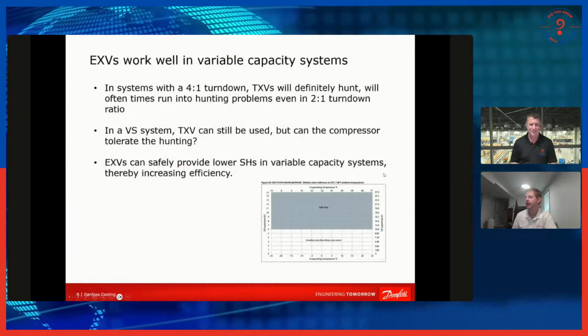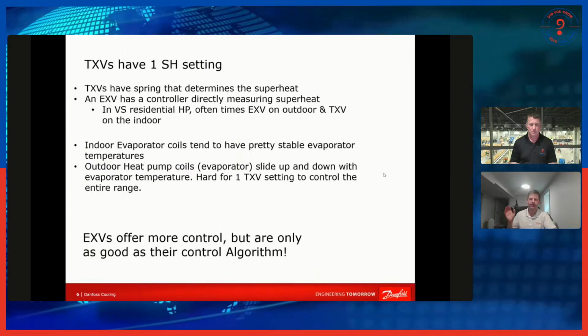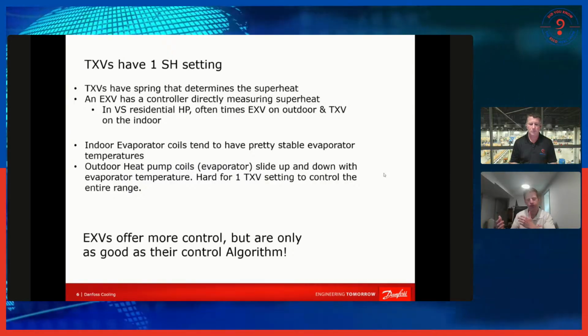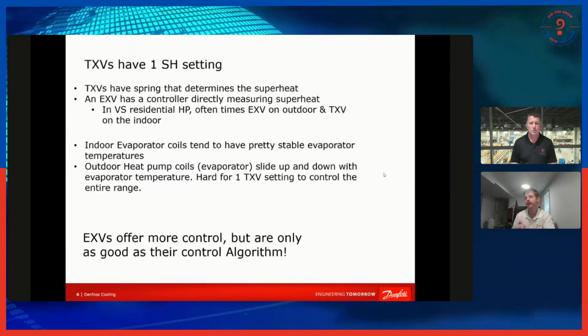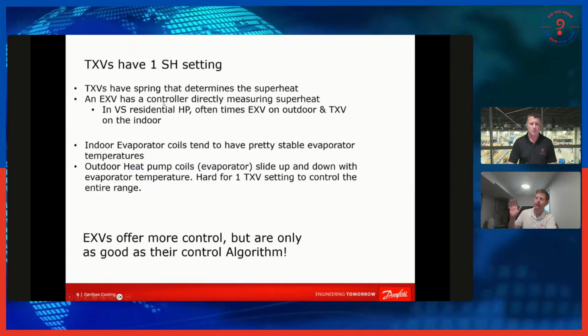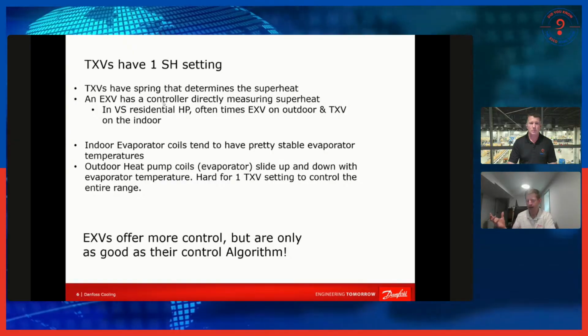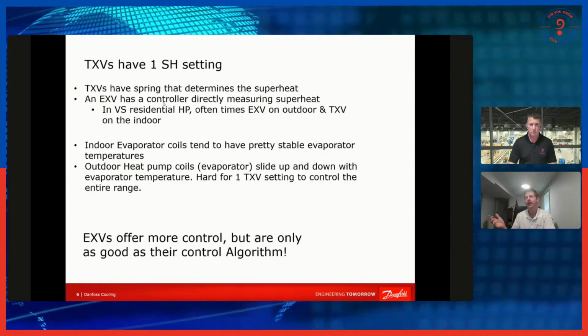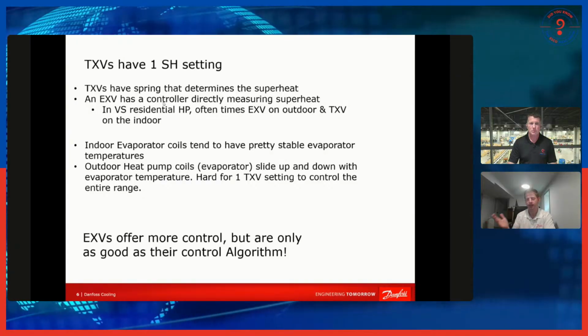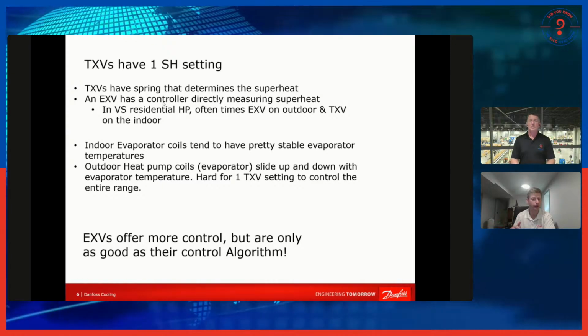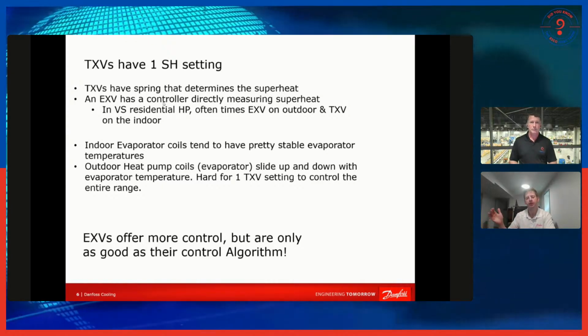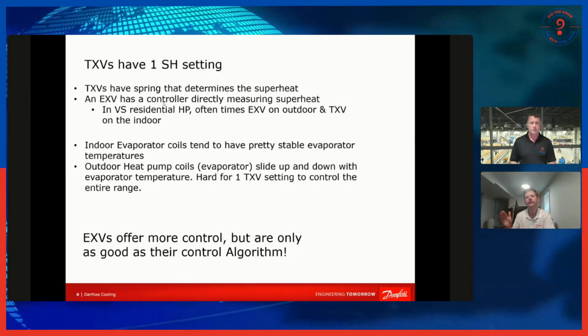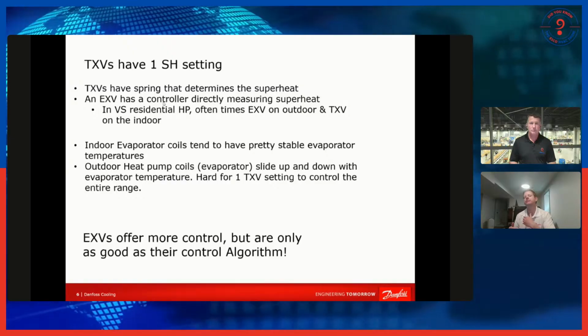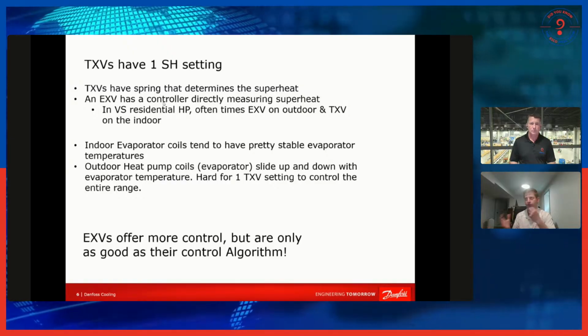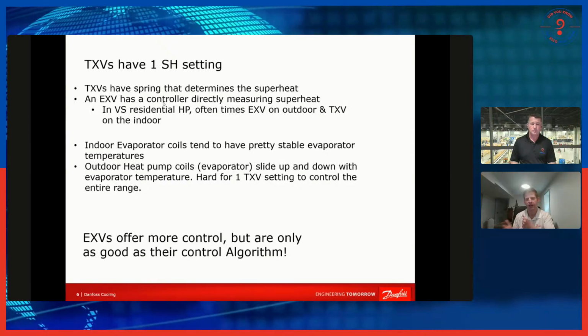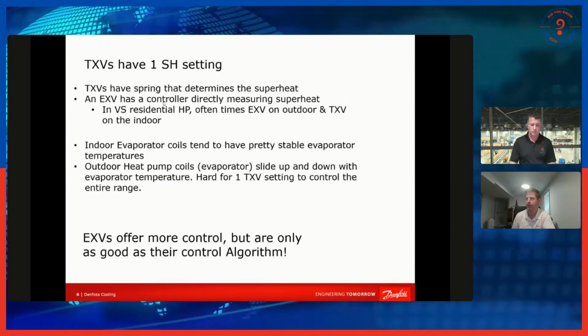And a TXV is going to have one setting, and that valve on its own will then measure and control to superheat based on that one setting. If you have an EXV, you're directly measuring superheat, and you've got a controller on there that's got an algorithm and a program in it. And whatever superheat it's controlling to, that can adjust in different seasons. It can adjust based on different loads. It could know, hey, when the compressor slows down, maybe I should let the superheat setting drift up a little bit higher. It gives the system manufacturer more options inside their controller for how that EXV should control based on other factors other than just what superheat is being measured at the evaporator.